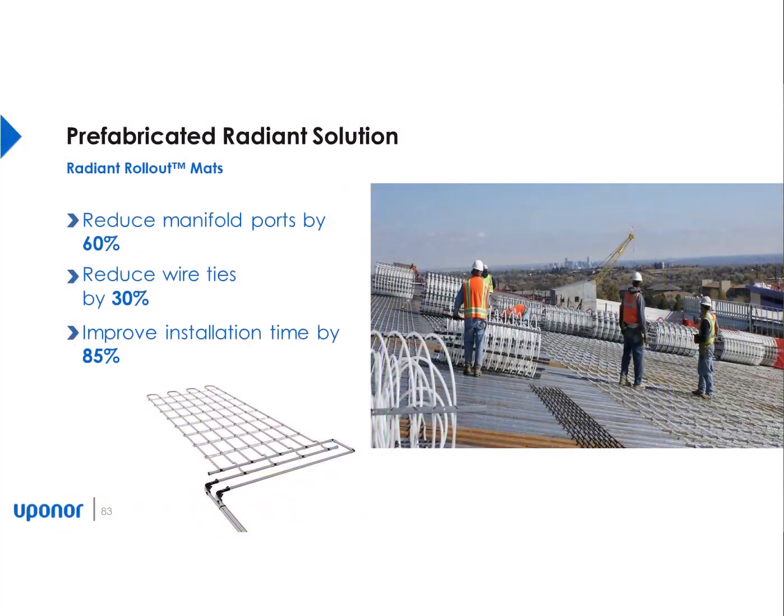Again, all three of these buildings had radiant floor heating, but this slide was left in because there were different strategies in place for heat recovery and delivering the air. And the takeaway here is that multiple opportunities for savings exist when you consider the entire system, not just the fuel source. And when you consider that installation labor is the largest cost in a radiant project, being able to significantly increase the efficiency of the installation can help save projects that may be at risk during value engineering exercises.